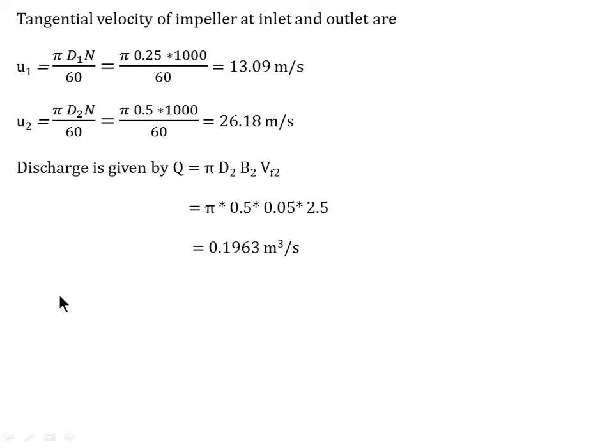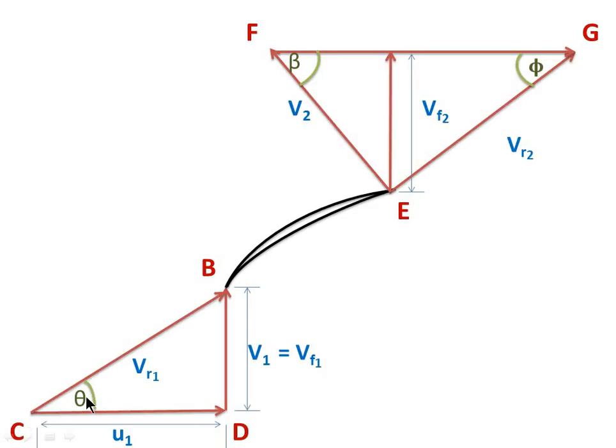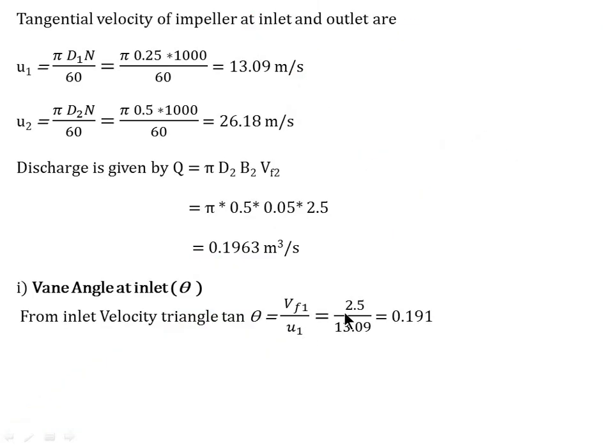The first parameter to calculate is vane angle at inlet, theta. From the inlet velocity triangle, tan(theta) equals Vf1 divided by U1. Since Vw1 equals 0, V1 equals Vf1. So tan(theta) equals 2.5 divided by 13.09, which equals 0.191. Therefore theta equals tan⁻¹(0.191), giving theta equals 10.81 degree.